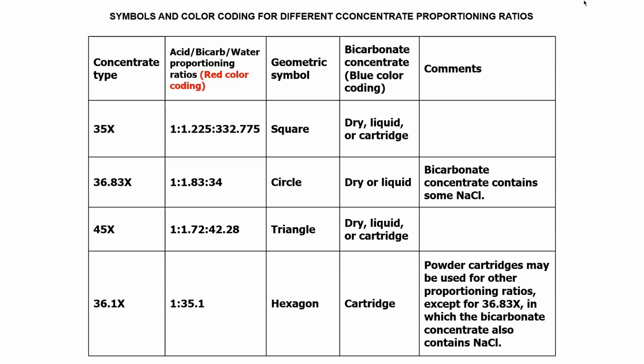The reason for that is that when the 3-stream system came about, we were still using acetate as a secondary, an alternative concentrate, where it was one connection, one job, or one concentrate, acetate. The facility at this place actually just converted over to the three-stream system. 3-stream is you got water, acid, and bicarbonate. They converted to the 3-stream, but guess what happened to the ordering pattern of the people that were ordering the supplies that didn't know about dialysis? They ordered the 45X acid. Their machine was still set up to be 35X.